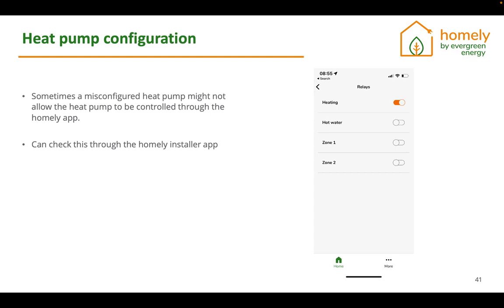Then we also ask installers to check whether the heat pump is able to do the things that it's told. So here, through the relays menu that I've shown before in the installer app, you can force the heating of the heat pump to turn on. What this does is disable the customer set points for half an hour, and it allows the engineers to do the commissioning checks on the heat pump. So if you toggle the heating on in this screen, the heat pump will go into heating mode, and it will also bump up the flow temperatures to 45 degrees so that you can check whether the 3-port valve is correctly connected.